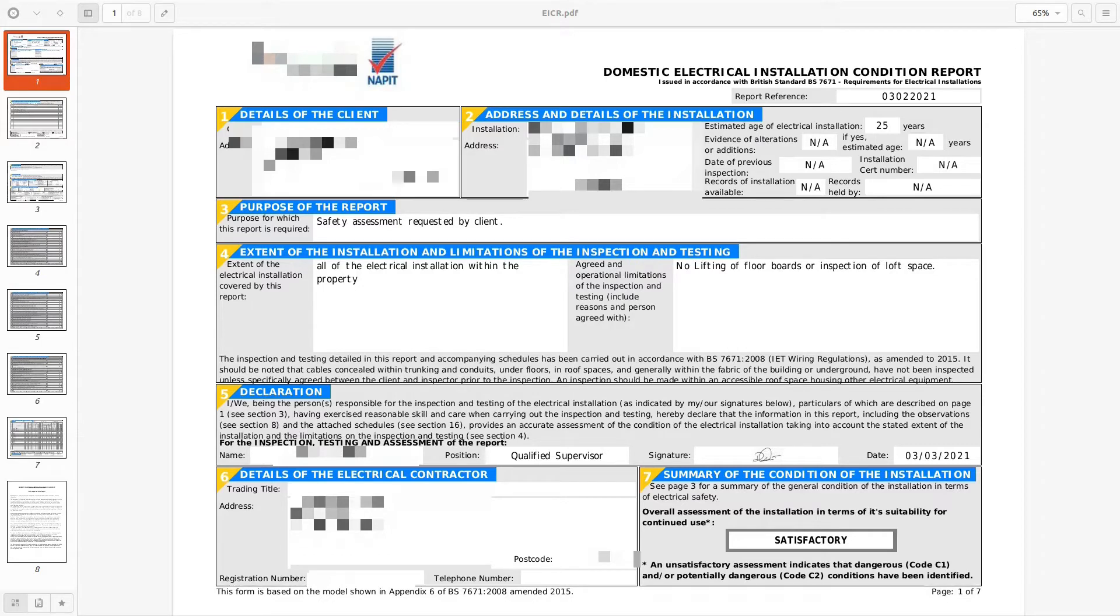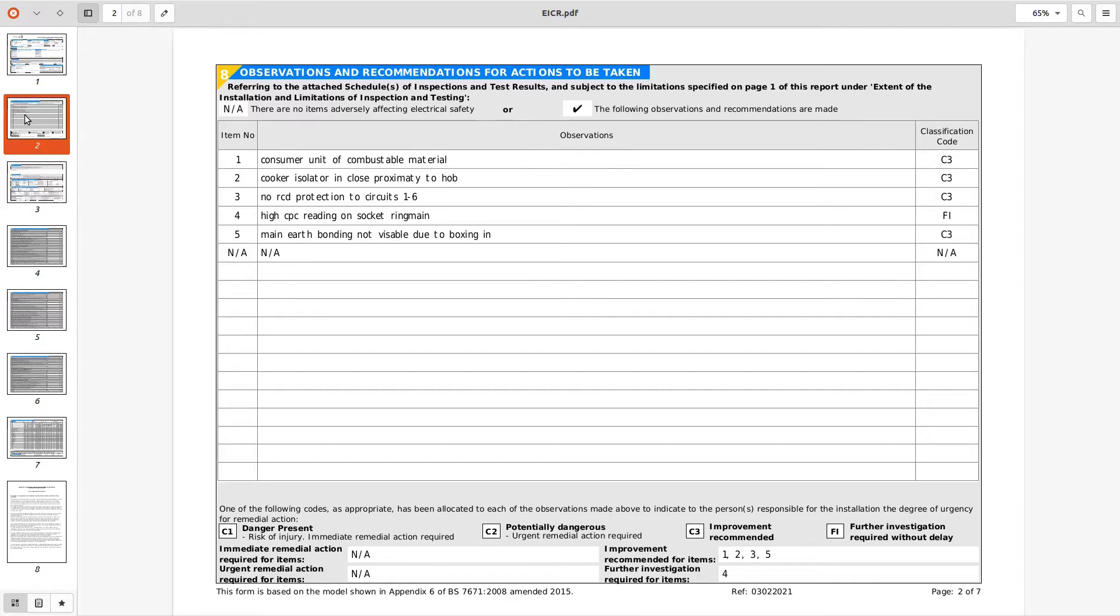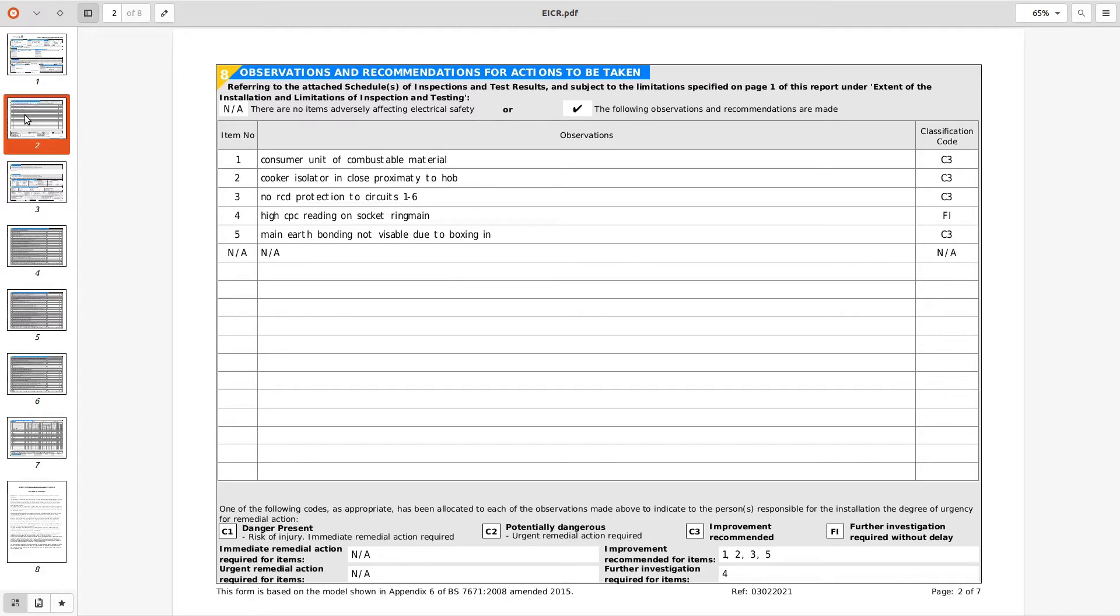The outcome of the installation that deemed as satisfactory. And looking at page 2 we've got some observations which are consumer unit is made of combustible material C3 seems reasonable based on the installation date. The cooker isolator in close proximity to the hob, that's not a code under BS 7671, used to be part of building regulations as a general rule of thumb adopted by the industry. So you could have listed as an observation, certainly no code required. So item number three is no RCD protection for circuits one to six.